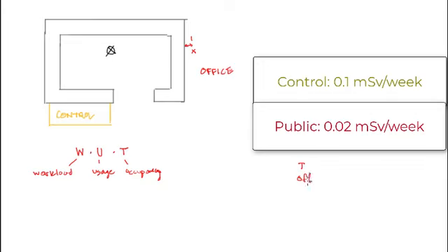So what are some occupancy factors? For the office it's 1. Somebody's always there. Exam room, the suggestion is to use a half, according to NCRP 151. A hallway, you use a fifth, and there are some other values in the report. And then we multiply this by B. So the B factor is the barrier transmission. What fraction of radiation is transmitted through the barrier?